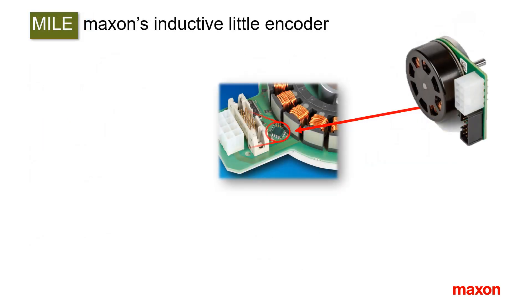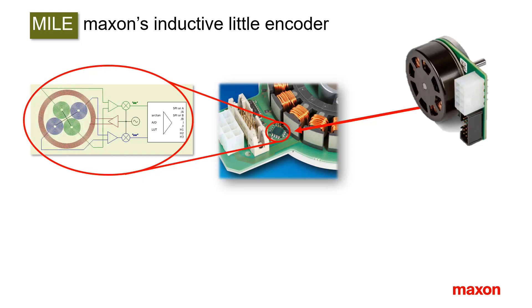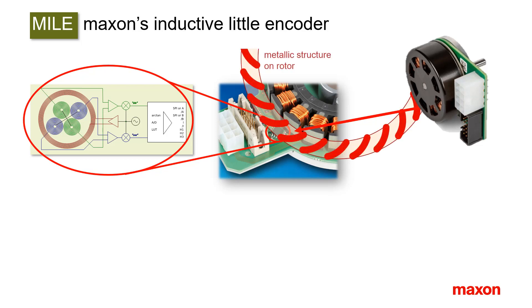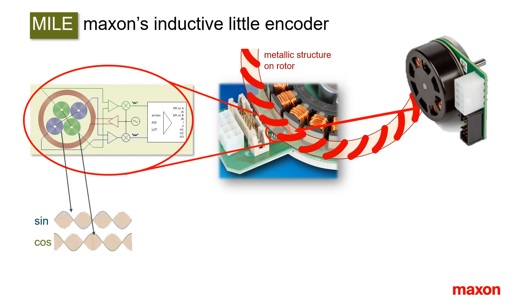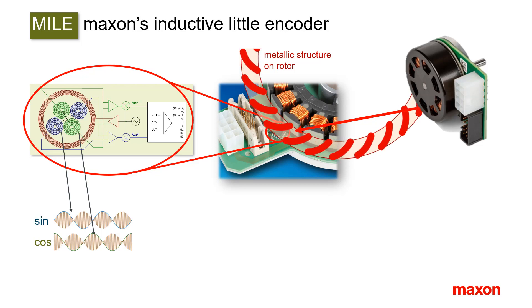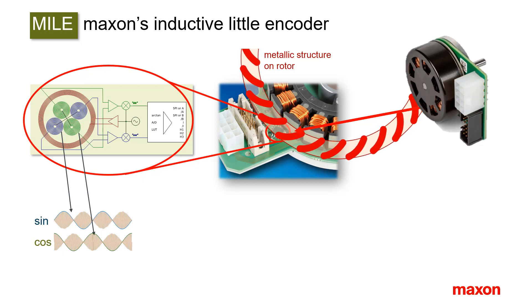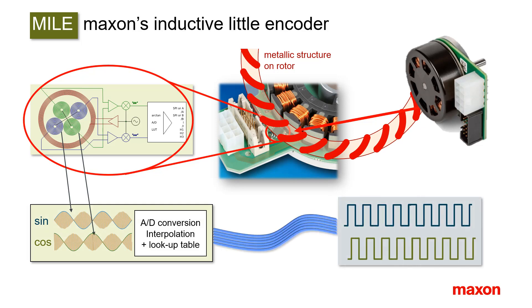The MILE is the perfect encoder to be integrated into flat motors. It contains all the electronics including a line driver in one tiny chip, and is based on an inductive physical principle. A high-frequency signal is transformed onto two pairs of pickup coils, modulated by a metallic structure on the rotor. Each section of the metallic target induces sine and cosine modulated signals in the pickup coils. An arctangent operation gives the rotor angle, and further signal treatment includes interpolation and production of rectangular encoder pulses. An adjustment process allows correcting the signal state width by means of a lookup table.